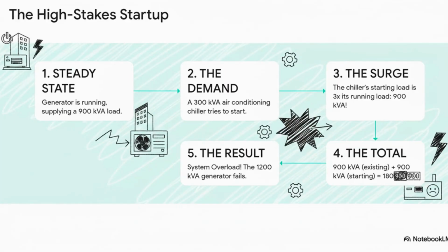Let's just walk through this little story. Your 1200 kVA generator is humming along, supplying 900 kVA of power. Everything's fine. Then a 300 kVA air conditioning chiller needs to start. But here's the kick.